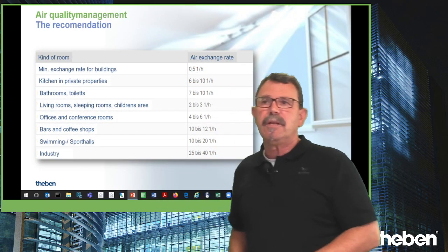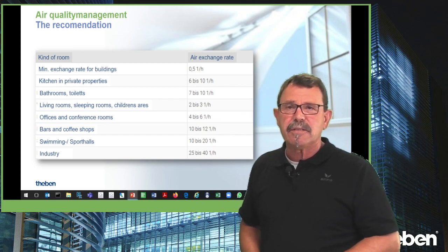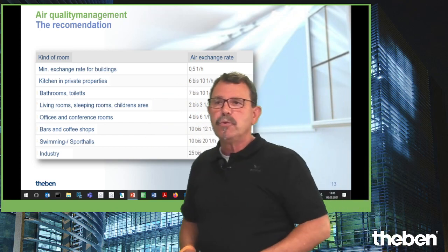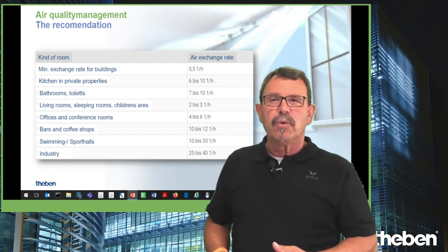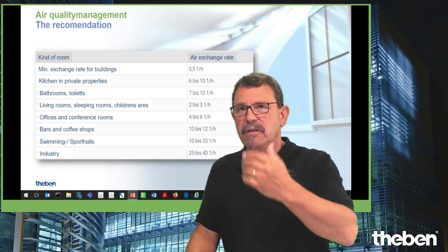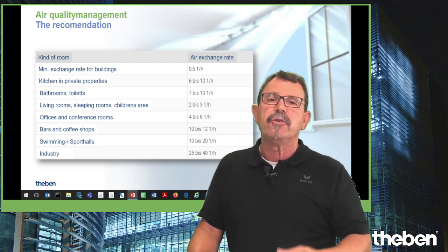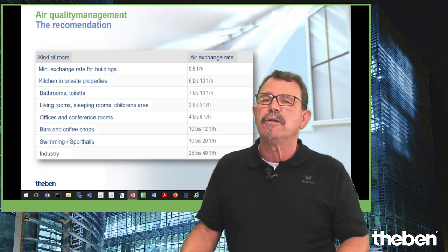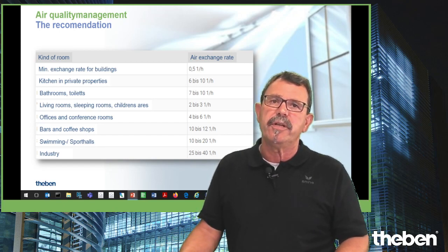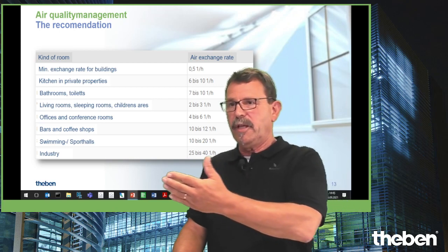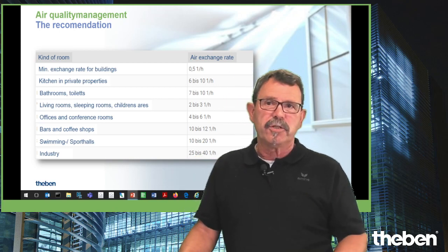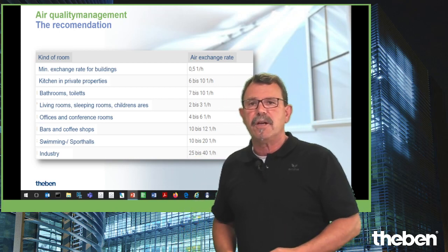There is a reasonable recommendation, which depends on the usage of the rooms: that at least half the volume of a room has to be exchanged within 1 hour, or in industry, it depends on what you're doing there, what you're manufacturing there.